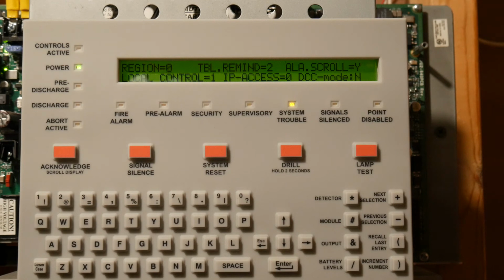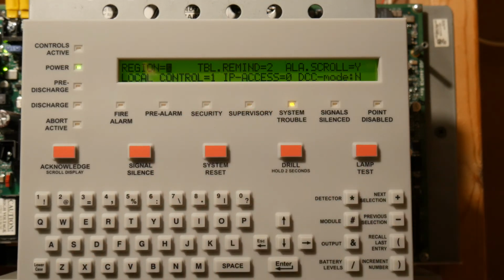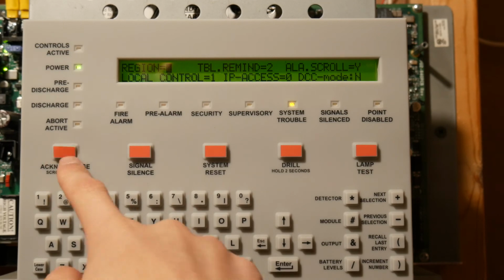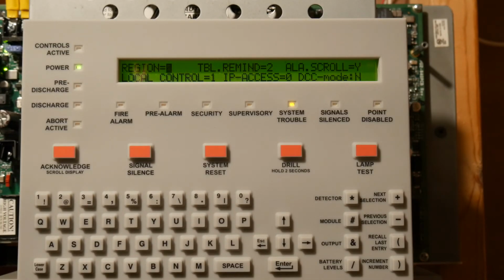Local control is basically how do you want your display to act. It could be local control 1, which means all the buttons work. Chicago style means only acknowledge and system reset work. And I do not know what everything else means. Oh, and also there's no control, which means none of the buttons work. But that's fine, so we're going to press enter.